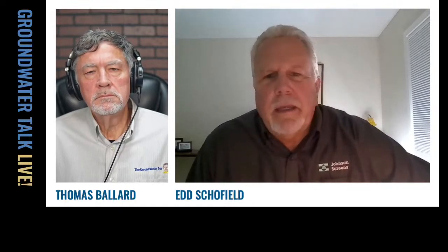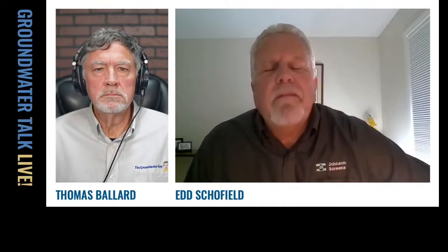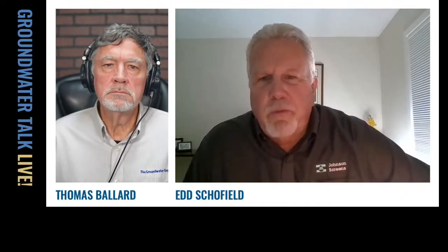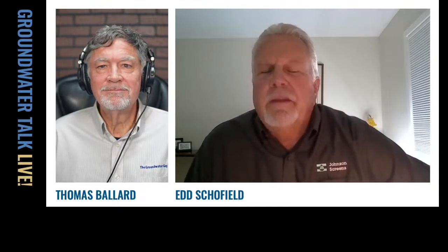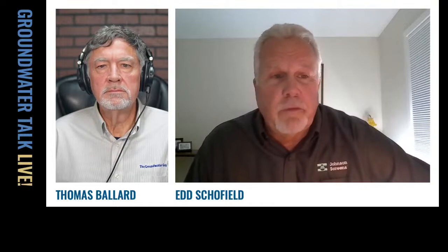So it's a CYA. You run that for your own confidence level, but you also run it from a standpoint of giving it a baseline, so that the next operator, the pump installer, whoever, can come back in and see whether or not someone has dumped a bunch of 4x4s down the well. Who's responsible if you don't have a video? And those videos, I've recently heard that somebody's come up with a portable video that's less than $1,000 now. And there's just no excuse not to have a video camera.